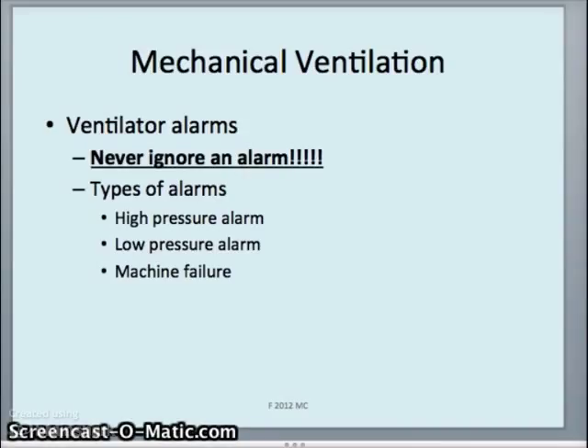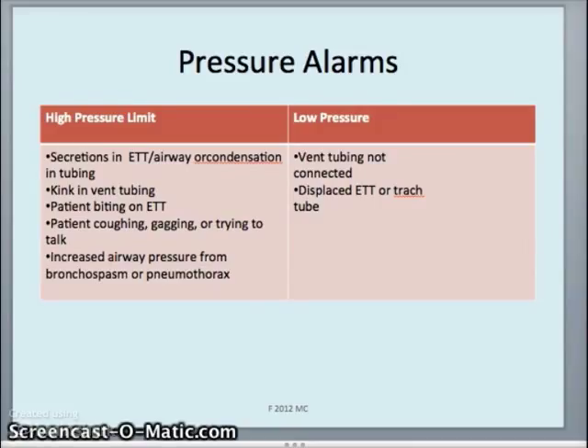So you need to be able to troubleshoot a certain amount of these, and a lot of them go off, and they're very simple fixes. So high pressure alarms are anything that prevent air from moving in or out. So anytime there's a blockage or something that's preventing the flow of the air to move easily, you're going to have a high pressure alarm. So frequently, high pressure alarms go off because there's secretions in the airway, okay? Which means you need to suction the patient.